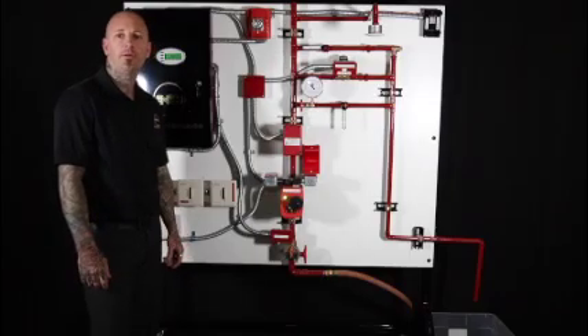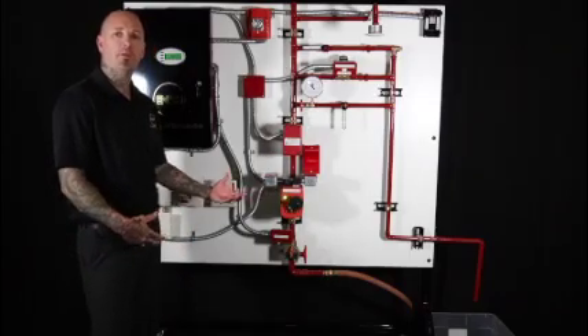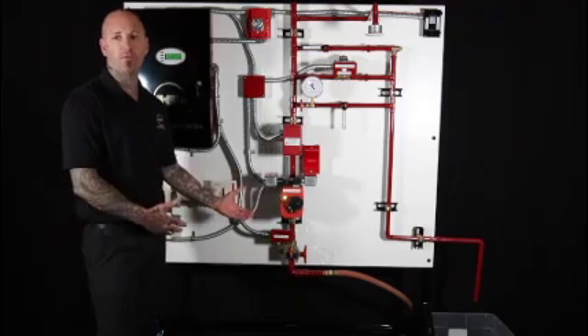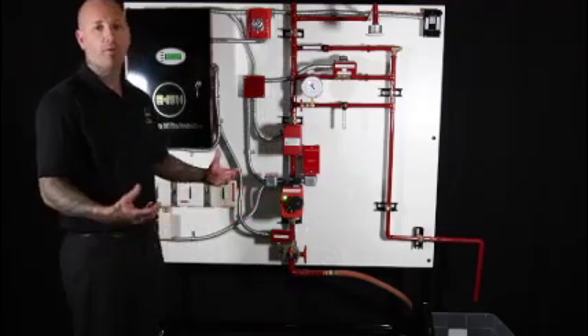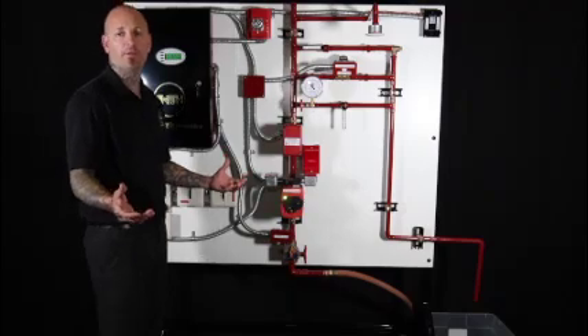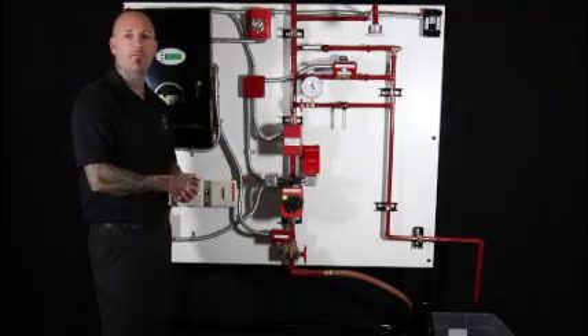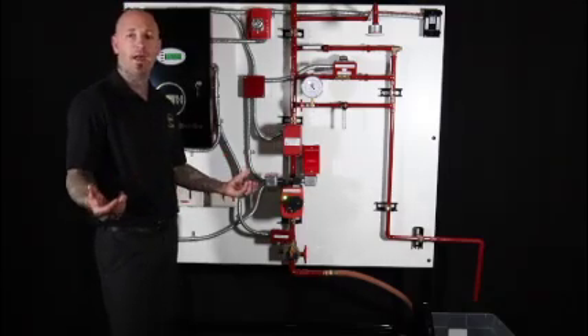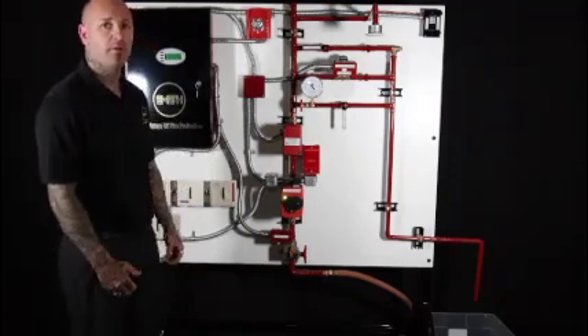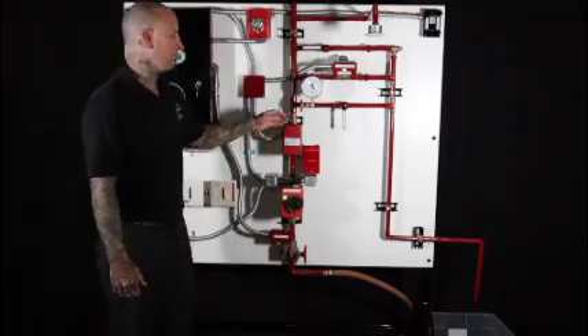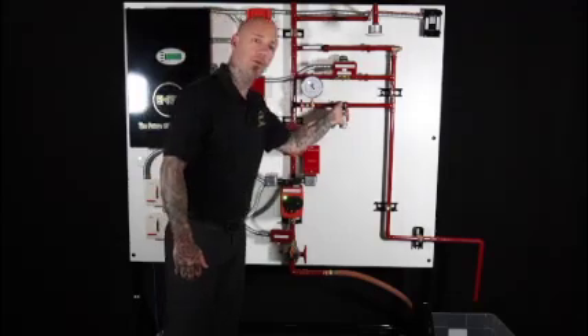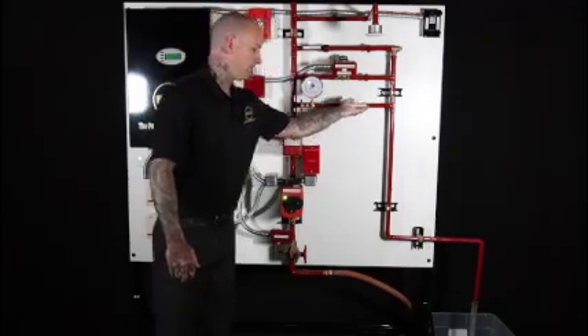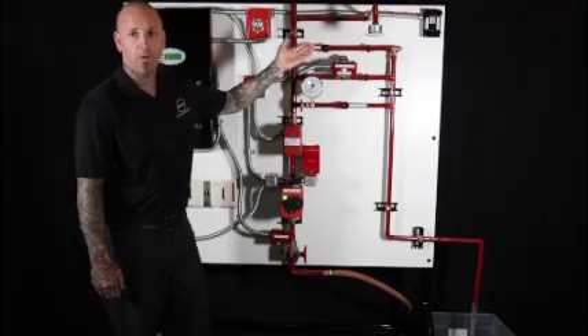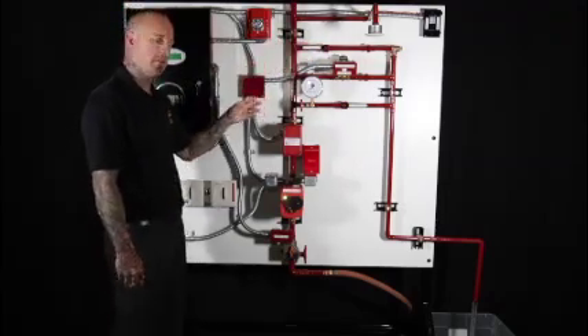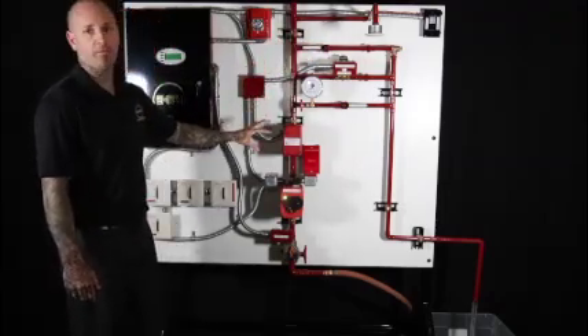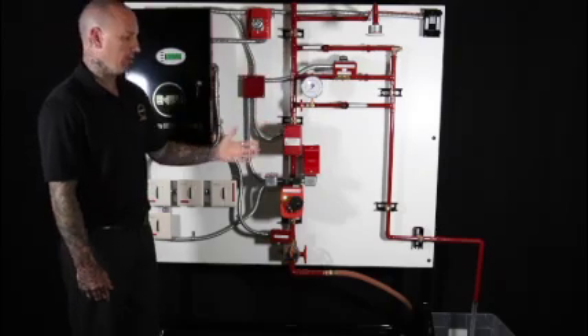Here in scenario 3, I like to demonstrate what would happen if we had a fire after we shut the water off. You'll have the water to the sprinkler system completely drained at that time, but then a head is activated by a fire that started after we shut the water off. I'll show you how that works. You have a broken sprinkler pipe, and you don't have a sprinkler head in alarm. So the system naturally is going to shut itself down and drain it all on its own.